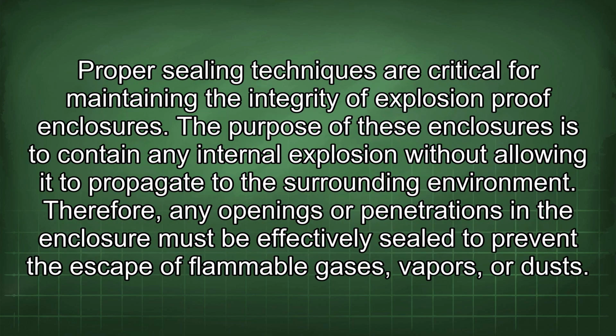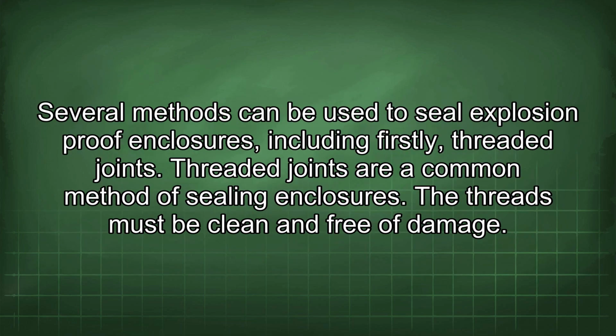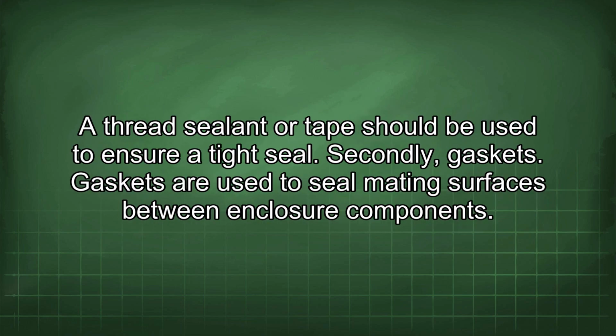Proper sealing techniques are critical for maintaining the integrity of explosion-proof enclosures. The purpose of these enclosures is to contain any internal explosion without allowing it to propagate to the surrounding environment. Therefore, any openings or penetrations in the enclosure must be effectively sealed to prevent the escape of flammable gases, vapors, or dusts. Several methods can be used to seal explosion-proof enclosures, including: firstly, threaded joints. Threaded joints are a common method of sealing enclosures. The threads must be clean and free of damage. A thread sealant or tape should be used to ensure a tight seal.